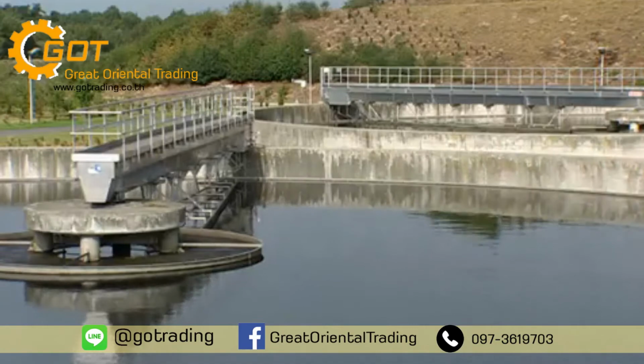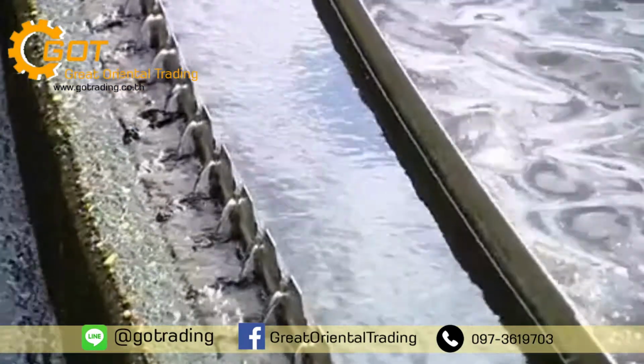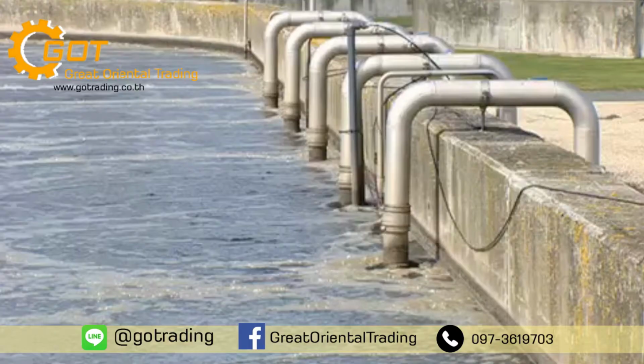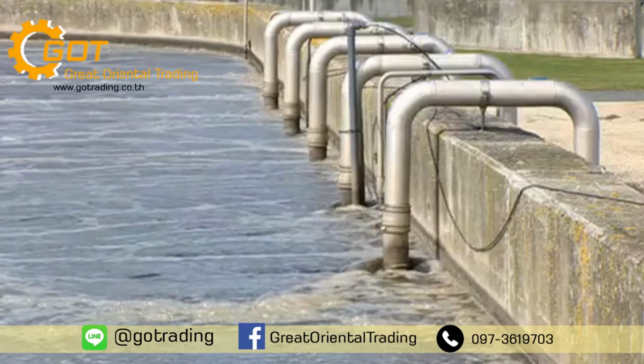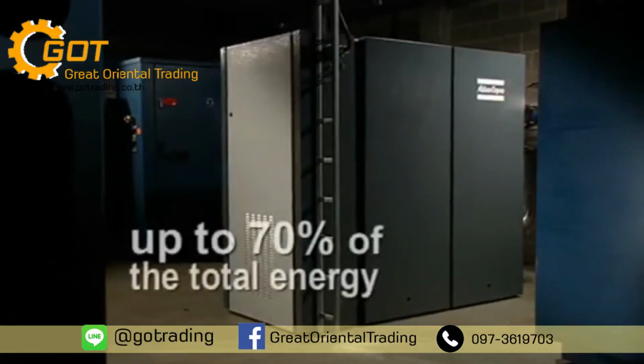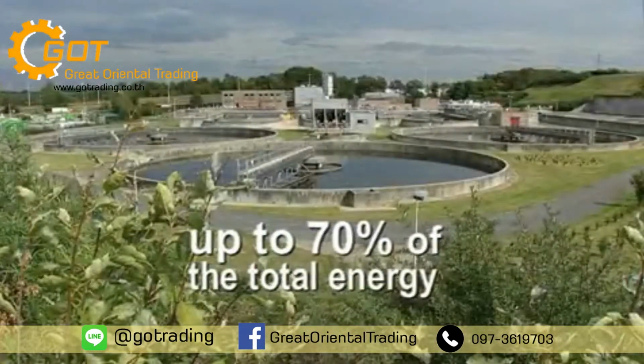In the final sedimentation, sludge is scraped from the bottom while purified water overflows and is led to the nearby river. The low-pressure air needed for biological cleaning is provided by blowers. These typically consume up to 70% of the total energy used in a wastewater facility.